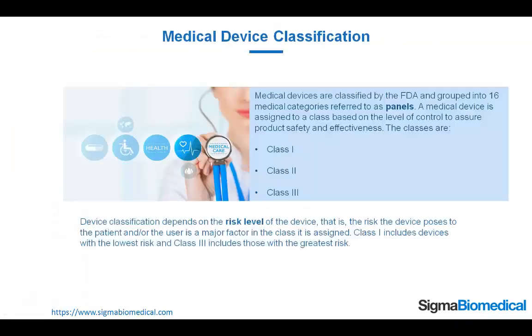Medical Device Classification. Medical devices are classified by the FDA and grouped into 16 medical categories, referred to as panels. A medical device is assigned to a class based on the level of control to assure product safety and effectiveness. The classes are Class 1, Class 2, and Class 3. Device classification depends on the risk level of the device — the risk the device poses to the patient and/or the user is a major factor in the class it is assigned. Class 1 includes devices with the lowest risk, and Class 3 includes those with the greatest risk.